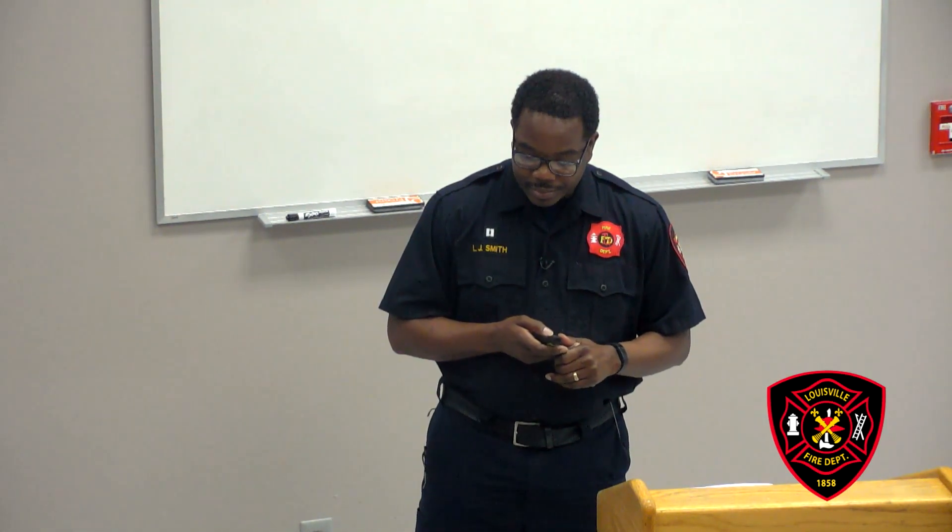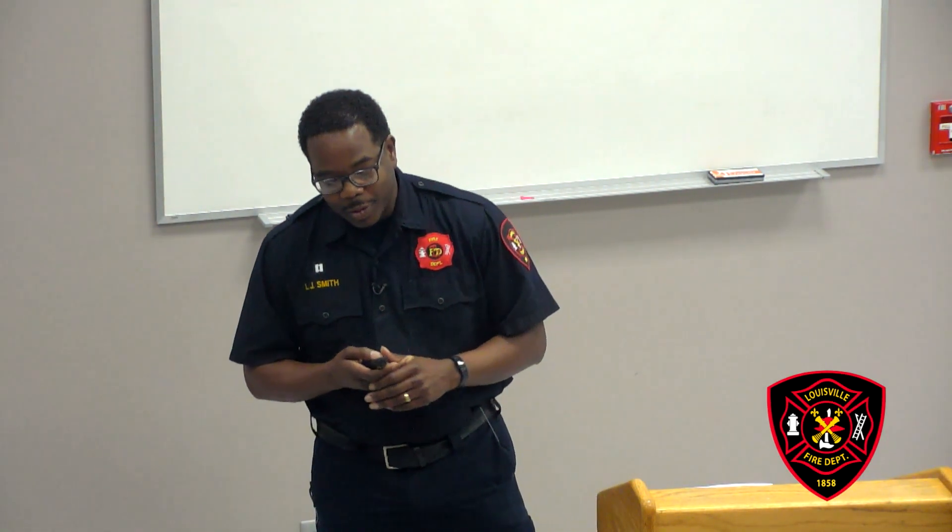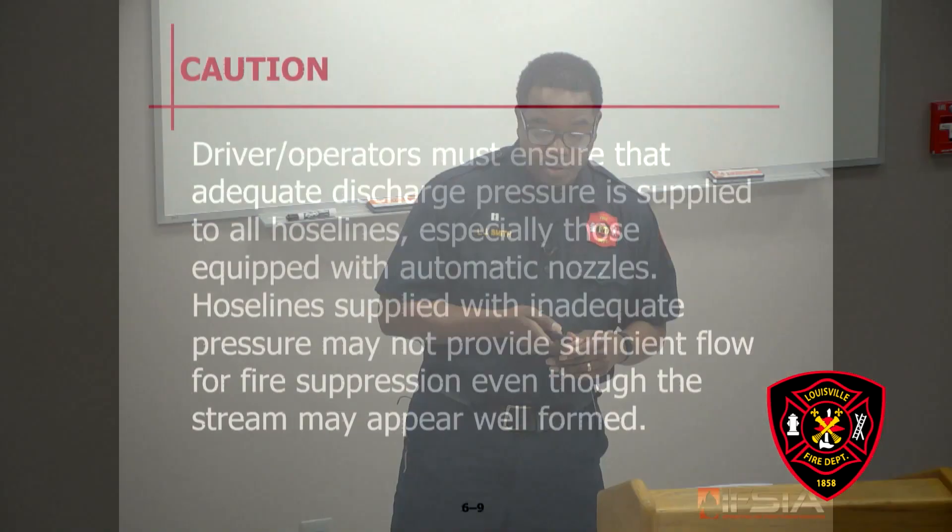The high pressure fog nozzle produces a stream with significant forward velocity but relatively low volume of water delivery. We typically don't use this in residential structure firefighting — these nozzles are used in wildland fires. The driver operator must ensure adequate discharge pressure is supplied to all hose lines, especially those with automatic nozzles, because inadequate pressure may not provide sufficient flow for fire suppression even though the stream may appear well formed.